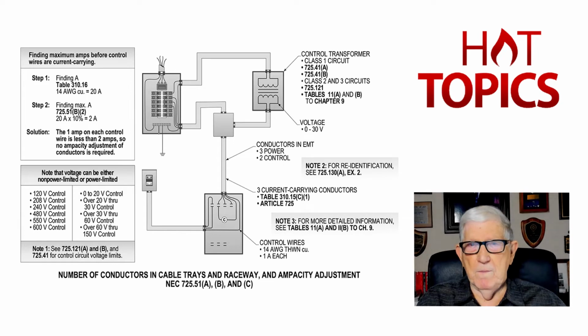in 725.121 of the code, you would go over to step 3, as you see here. In step 3, maybe it's a better word, you'd pick up your Tables 11A and 11B, and that would give you those outputs that you see in the illustration to the left at the very bottom. Now, we're not really worried that much about a class 2, like the chimes in your home. That's usually a class 2 circuit. It's not harmful to you.